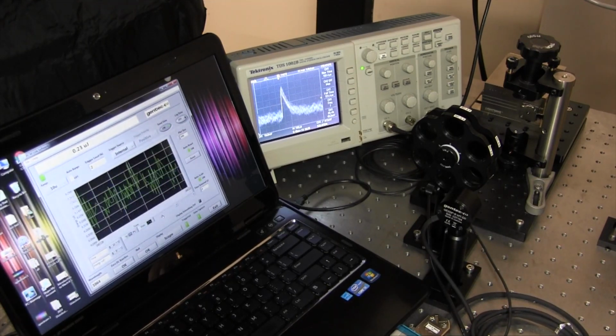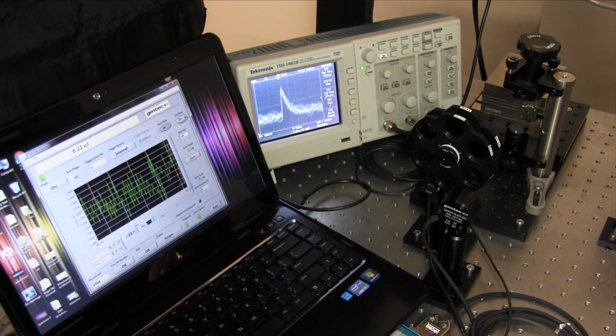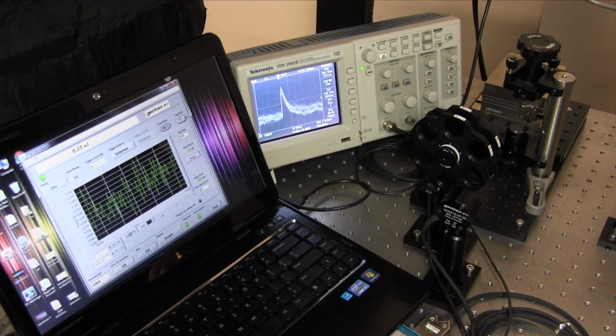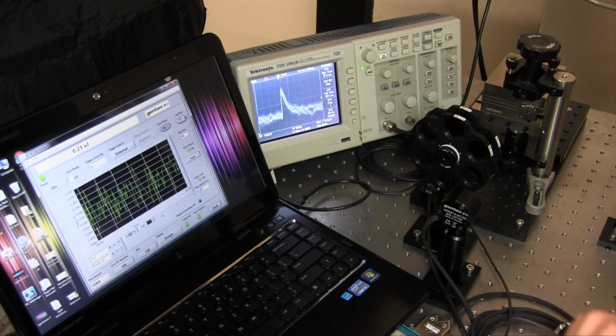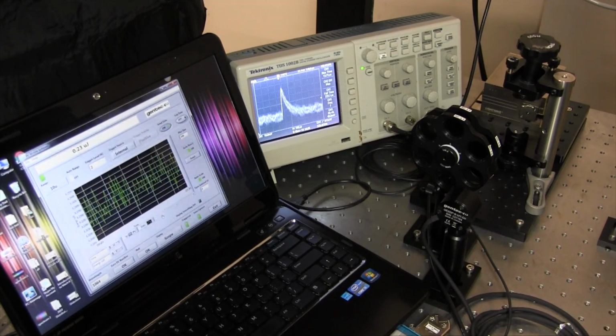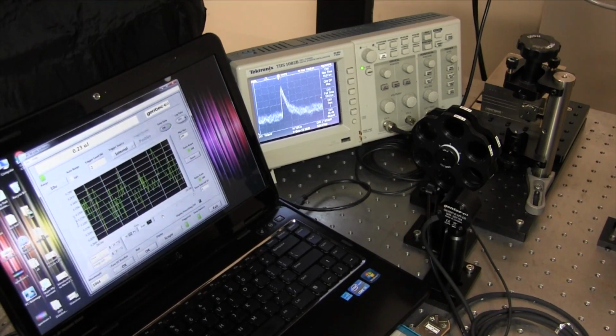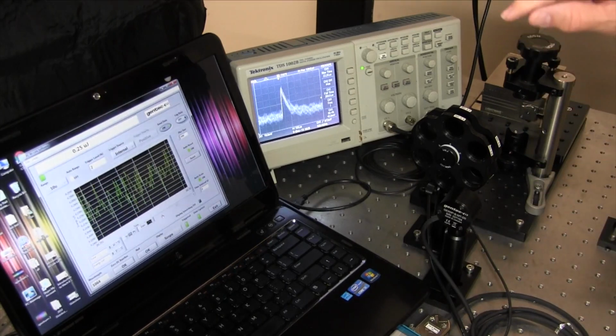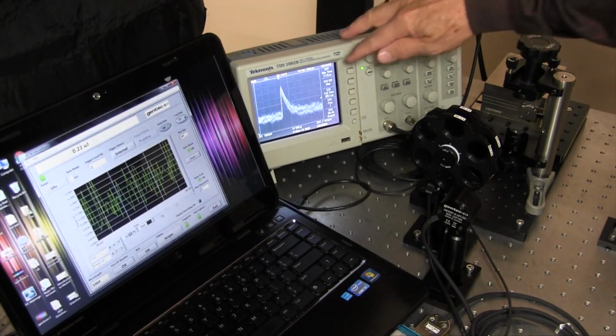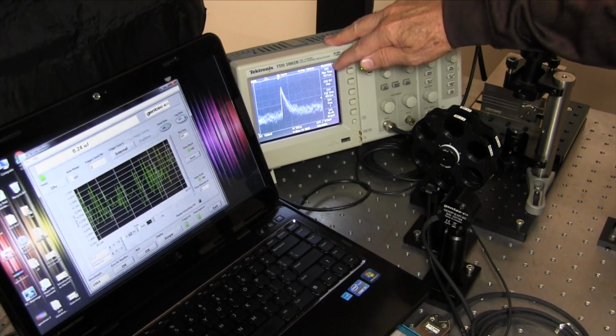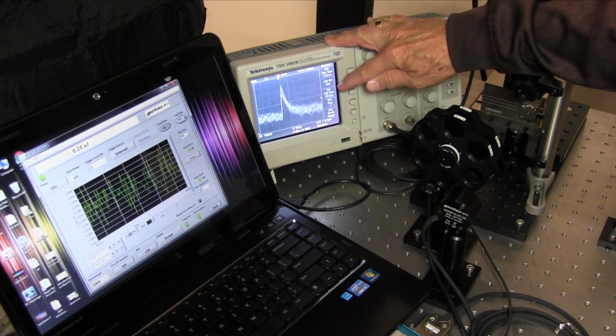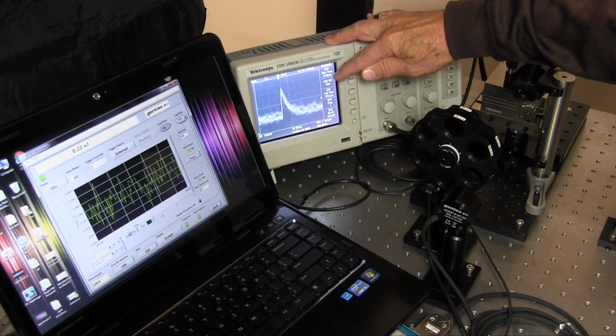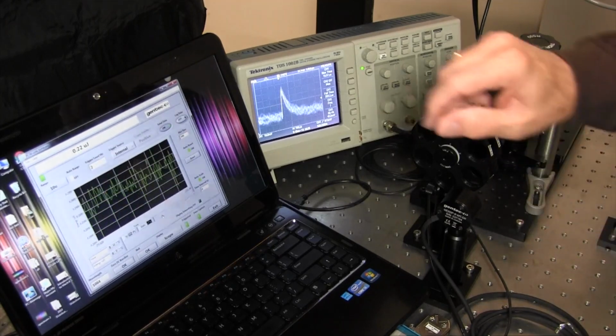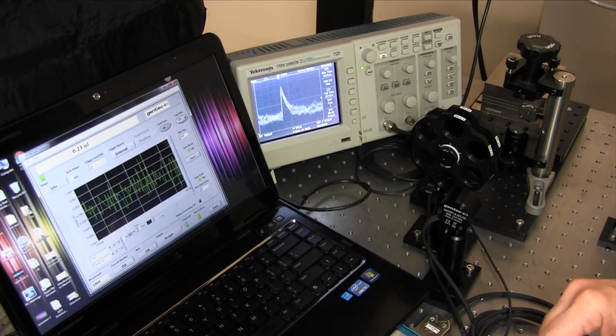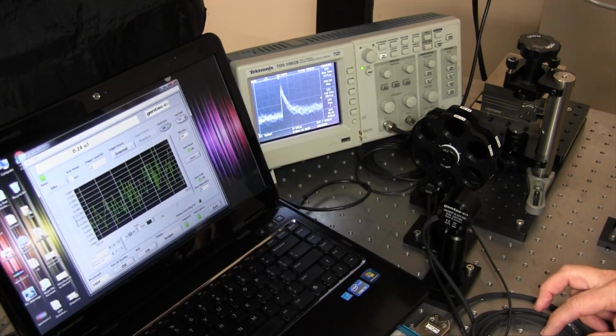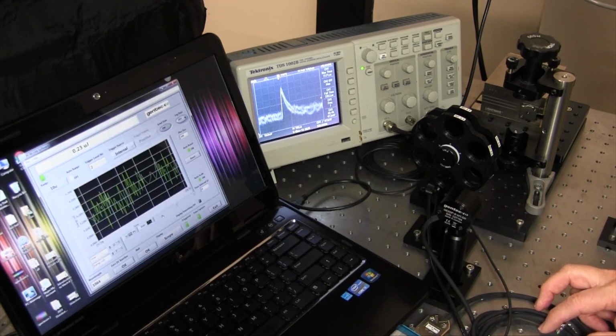I've moved the ND filter into place to attenuate the laser such that we're making measurements on the lowest range at about 0.23 microjoules, so 200 nanojoules. You'll notice that the analog output is not very clean. It contains a lot of high frequency noise and fluctuation. I've set the trigger level at 2%, but we're still having trouble getting a good stable reading.